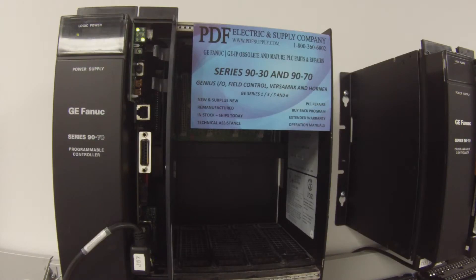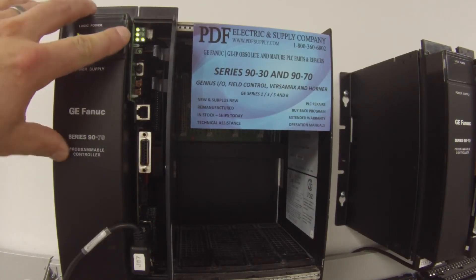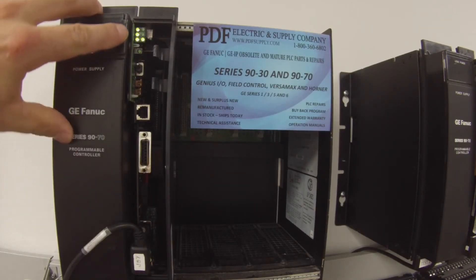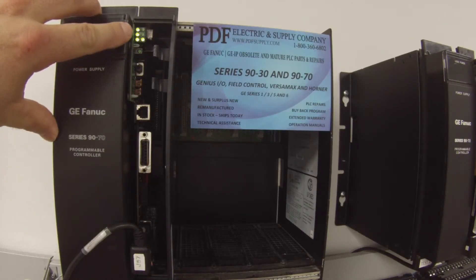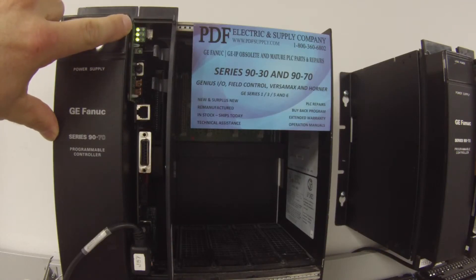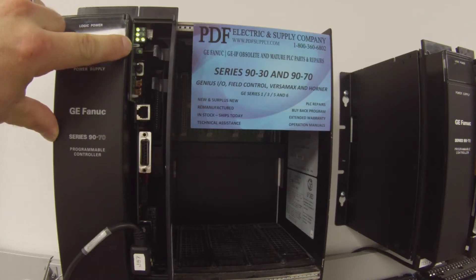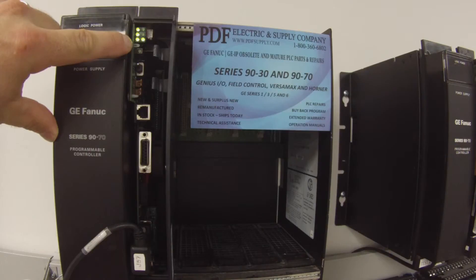Once this build is completed, allow me to get the processor into run mode, which is the goal here. I want to make sure that the processor can go into run — and it has. These three LEDs: the first one is processor OK, that's the important one from the beginning. The second one is run mode, and the third one is IO enabled — inputs and outputs enabled.